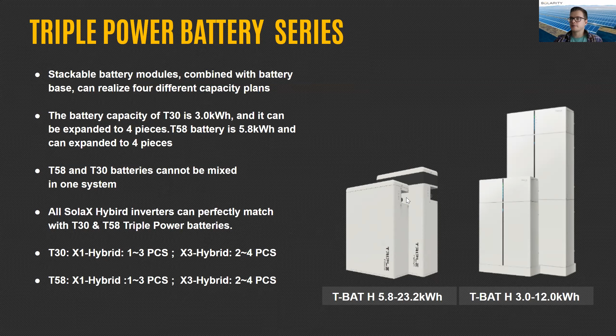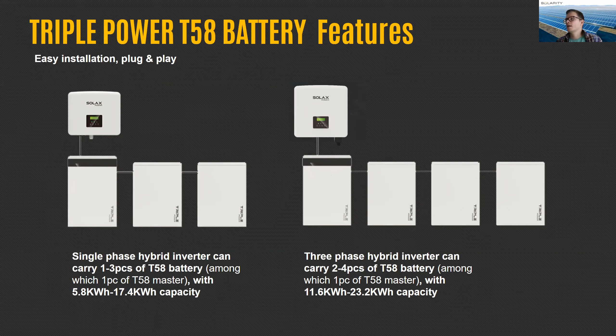So you need to make sure that if you are installing the T-Bat 5.8 battery, and it's just one unit, it should be the master unit, right? And if you have 2 units, that should be master and slave, like here, for example. For the single phase solution, a maximum of 3 pieces can be connected, which will give you 17.4 kilowatt hours of capacity. And for the 3-phase hybrid solution, up to 4 pieces can be connected, which will give you a total capacity of 23.2 kilowatt hours.